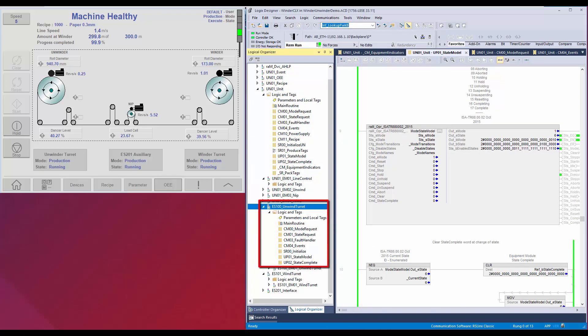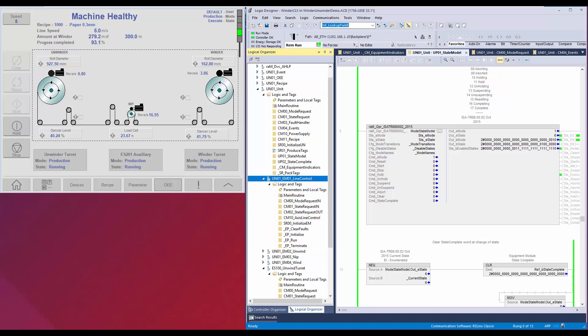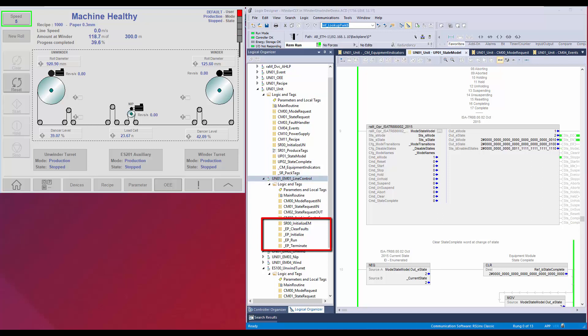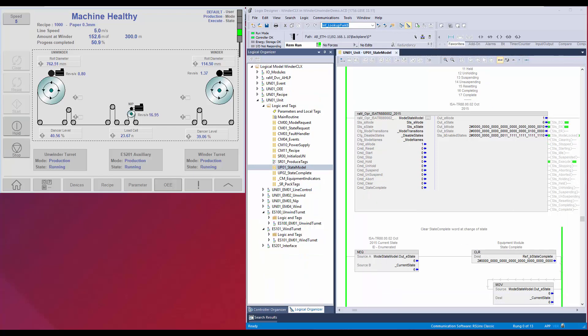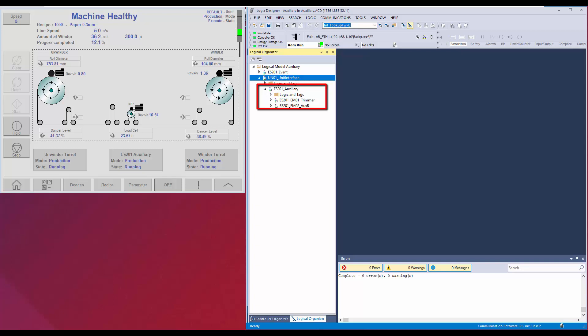The equipment supervisor program also has a similar routine arrangement as the unit. The equipment supervisor has additional code for operating under unit control or under local control. The equipment modules under unit or equipment supervisor are all the same. Each equipment module has routines for mode and state, status in and out. User can add the action logic for each state in these routines. Additional routines can be added as necessary per user requirement. This is the interface program for auxiliary equipment supervisor. This is the second controller. Here you can see the unit interface. Under the unit interface is the equipment supervisor and the equipment modules.